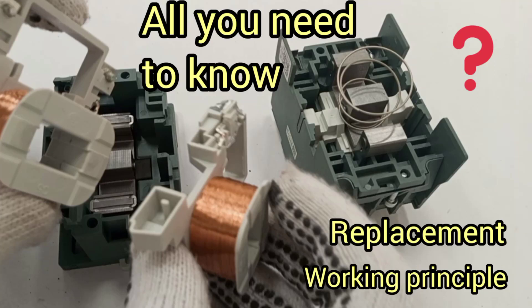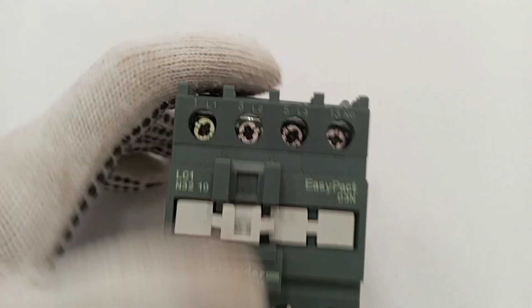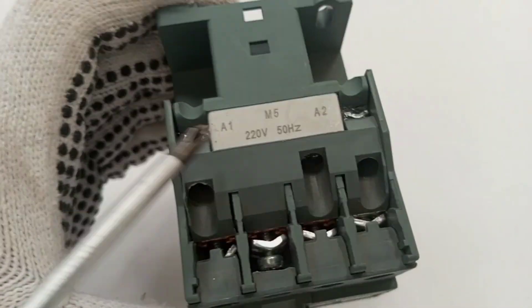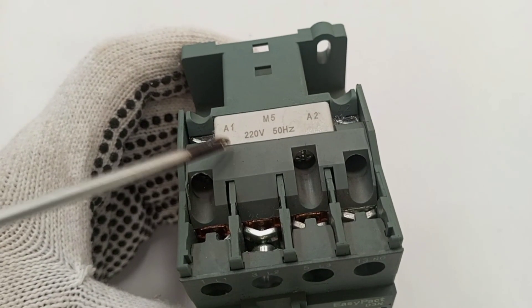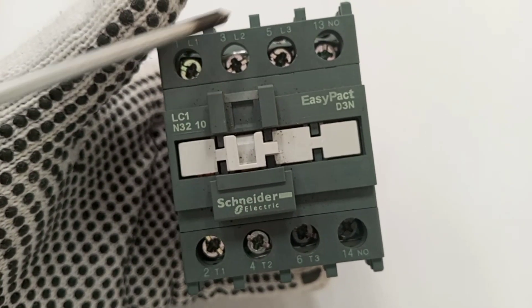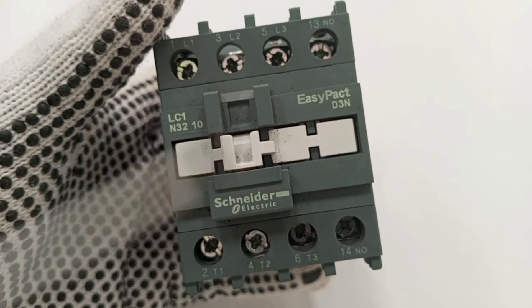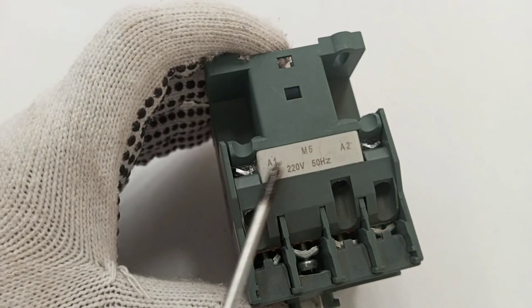My dear friend, welcome to my channel. In this video, I'm going to practically show how to replace a contactor coil. This is a contactor and it has a coil. It is this coil that gets magnetized to close the contacts of the contactor to the load. When the coil goes bad, you can easily replace it.